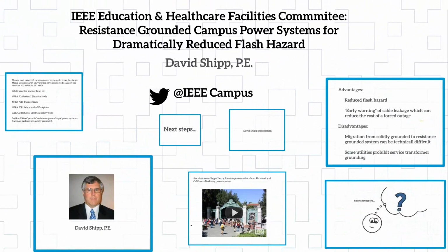In fact, I was doing it in a pharmaceutical research facility in the New Jersey area about 5 years ago, and every 2 feet there was another panel board running a different thing. There's probably 50 panel boards in one little bitty hall, and they were mislabeled too. They said they were like category 4, and I'm looking at a 15 kVA transformer feeding it. This is where the 125 kVA rule is very dominant. And I said, well, whoever did your arc flash study didn't know what they were doing, but I went through a lot of the things they could do, and they're looking at it.